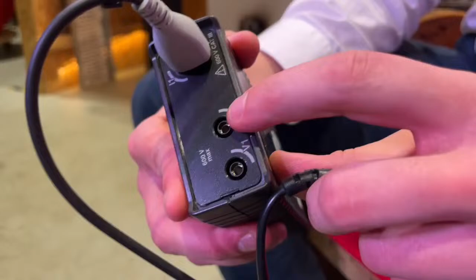Ultimately, you've got two 4mm sockets here, banana plugs that you can connect directly to your live and neutral, or we have a CT socket here for the current side. It's bi-directional, so we can see the solar side with that unit. It's really a good little unit - it captures every 1 second, so we can do maximum demand stuff and various different things we'll go into a little later with that unit.